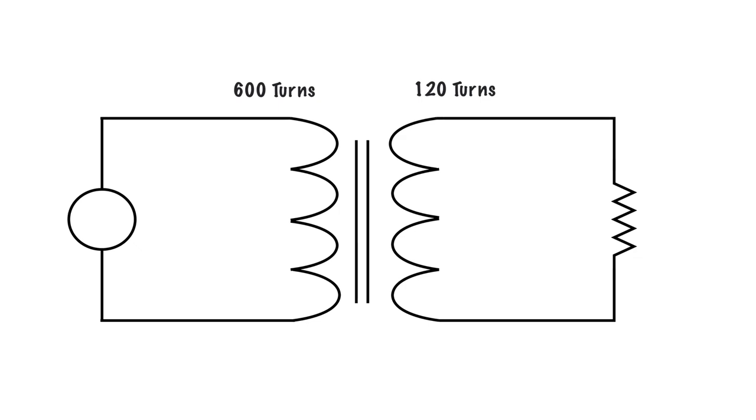So what we need to do is figure out what our turns ratio is. And the easiest way to do that is just take the higher number and divide it by the lower number. Always the higher number divided by the lower number. It doesn't matter if it's step-up or step-down.